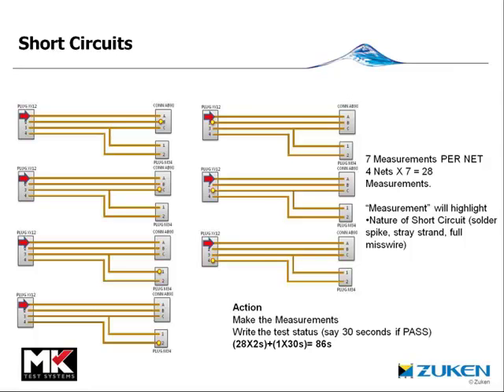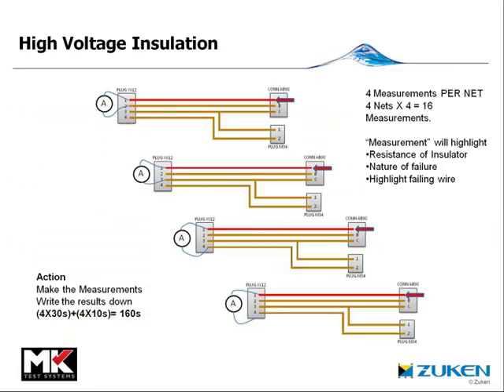Moving on from short circuit tests, the test that is very rarely done with manual testing is high voltage insulation measurement. These are performed to check the health and state of the insulation of each core. Automatic testing would charge each core in turn and measure current leakage into all other cores shorted together — the one-against-all test. By hand, the only feasible way is the old megohmmeter-type test where each core is charged in turn and we measure for current leakage into the other cores one at a time. This process is slow and prone to error, with a minimum of 160 seconds for the high voltage check.